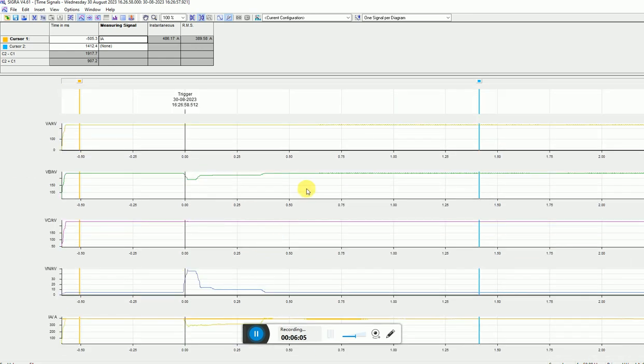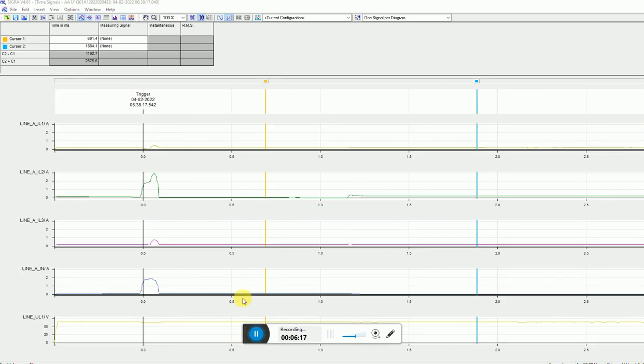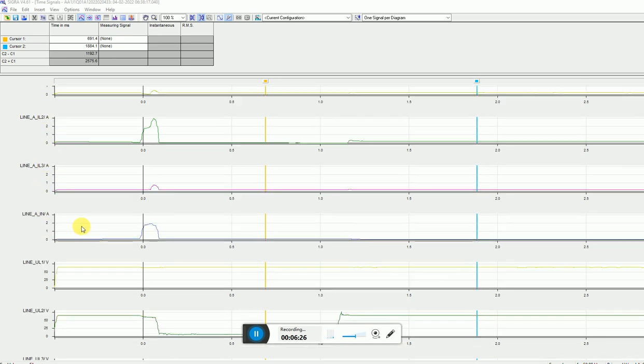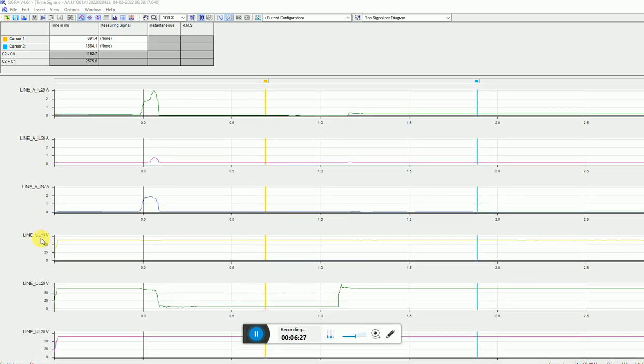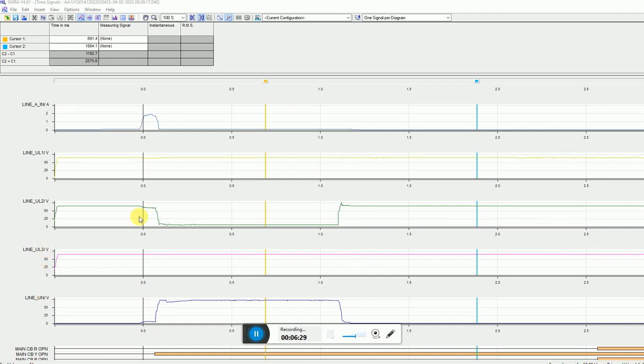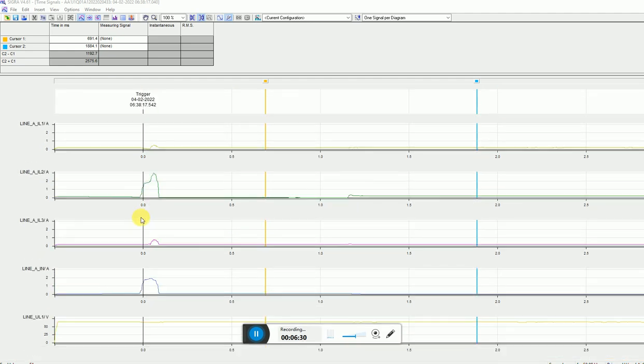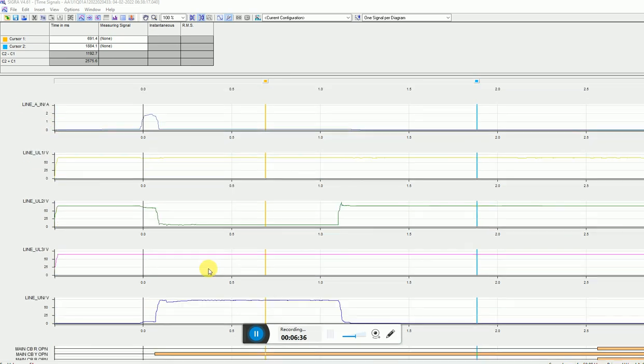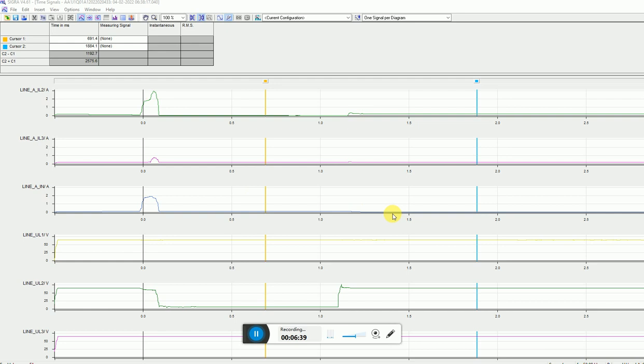Let us see one fault DR, what happened to the relay when there is a fault. We will analyze one fault DR. I have already one fault DR. I will show you. Here you can see one fault DR, that is distance relay. This DR belongs to R phase, Y phase, B phase current. This is R phase voltage, Y phase voltage, B phase voltage. Here you can see nomenclature got changed L1, L2, L3, but in MiCOM IA, IB, IC.